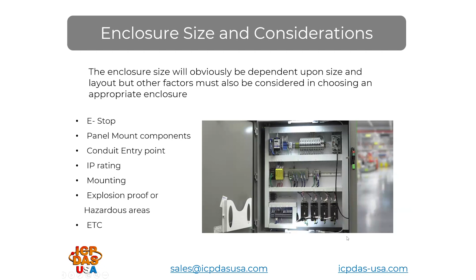If an HMI or other panel mount devices are going to be part of the control cabinet, be sure to install proper gasketing and follow the manufacturer's standard cutouts for instrument and control components. For these components, also be sure to allow proper depth of panel for proper airflow and spacing to allow for good electrical wiring practices.